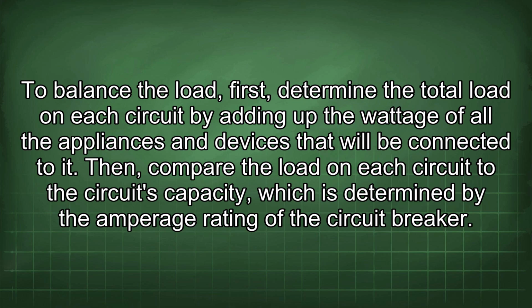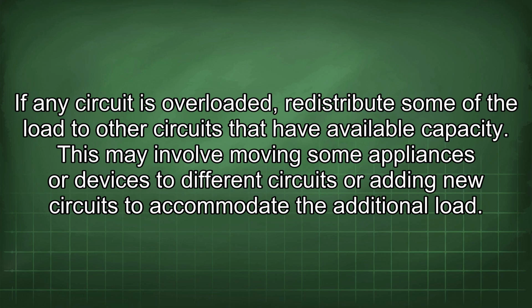To balance the load, first determine the total load on each circuit by adding up the wattage of all the appliances and devices that will be connected to it. Then compare the load on each circuit to the circuit's capacity, which is determined by the amperage rating of the circuit breaker. If any circuit is overloaded, redistribute some of the load to other circuits that have available capacity. This may involve moving some appliances or devices to different circuits or adding new circuits to accommodate the additional load.